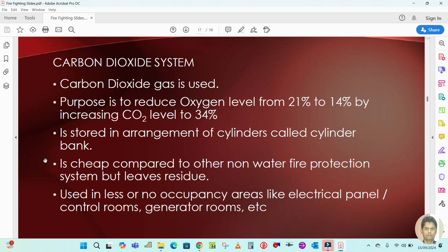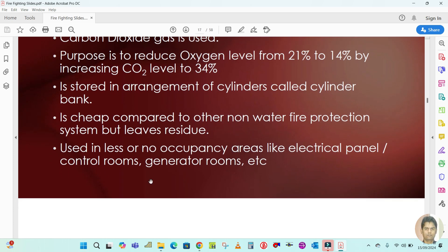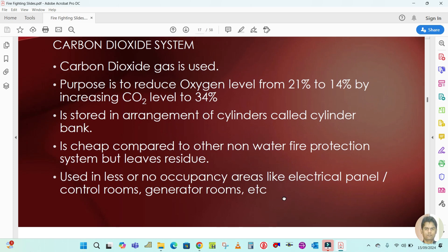It is stored in an arrangement of cylinders called a cylinder bank. It is cheap compared to other non-water fire protection systems, but it leaves residue. It is used in less or no occupancy areas like electrical panels, control rooms, generator rooms, etc., where there is no occupant available.